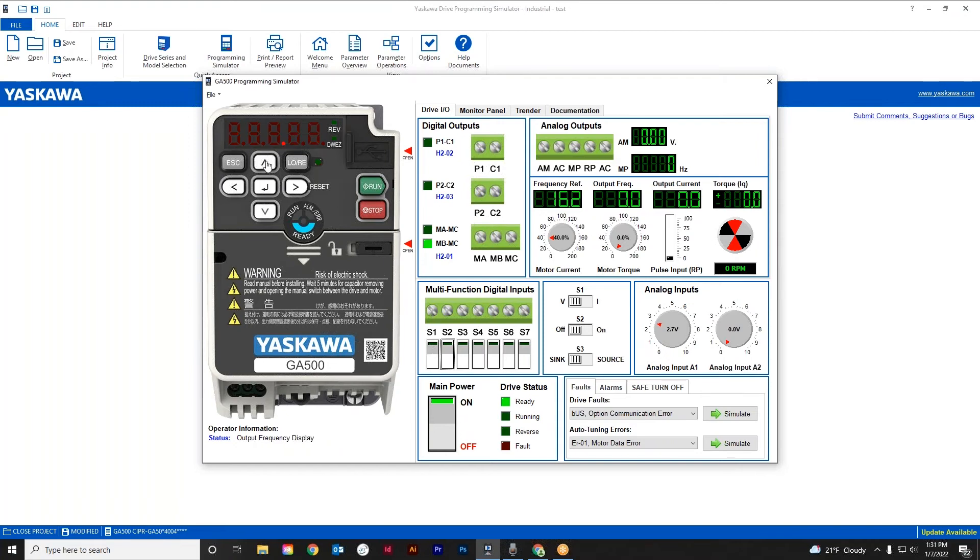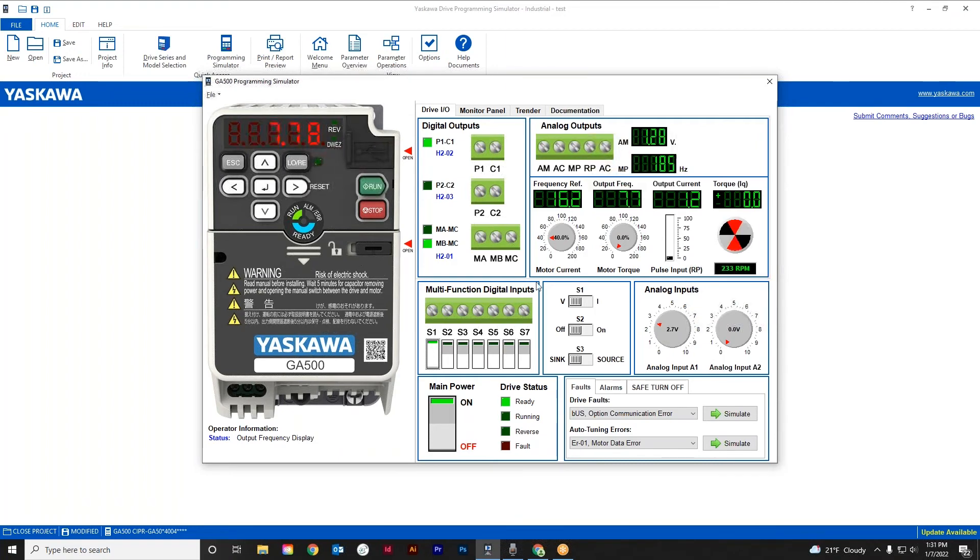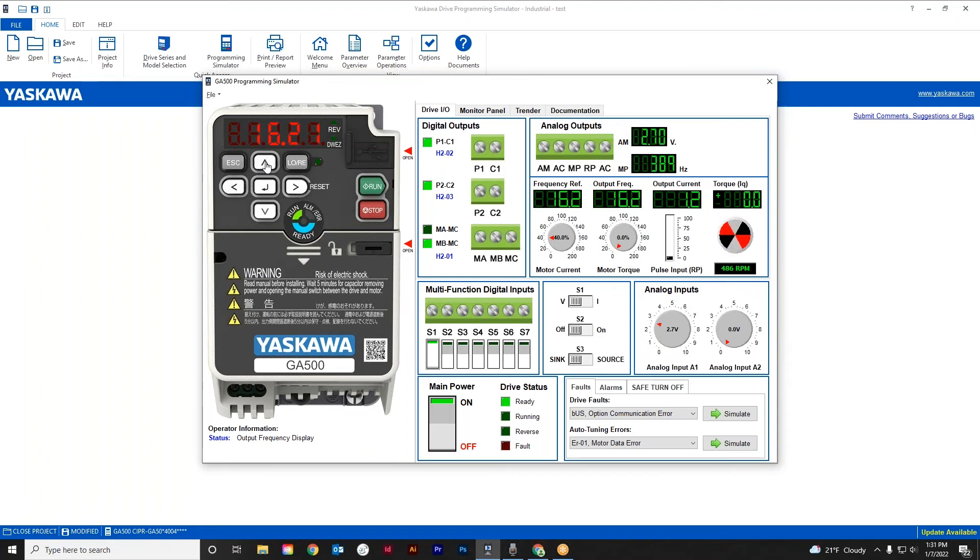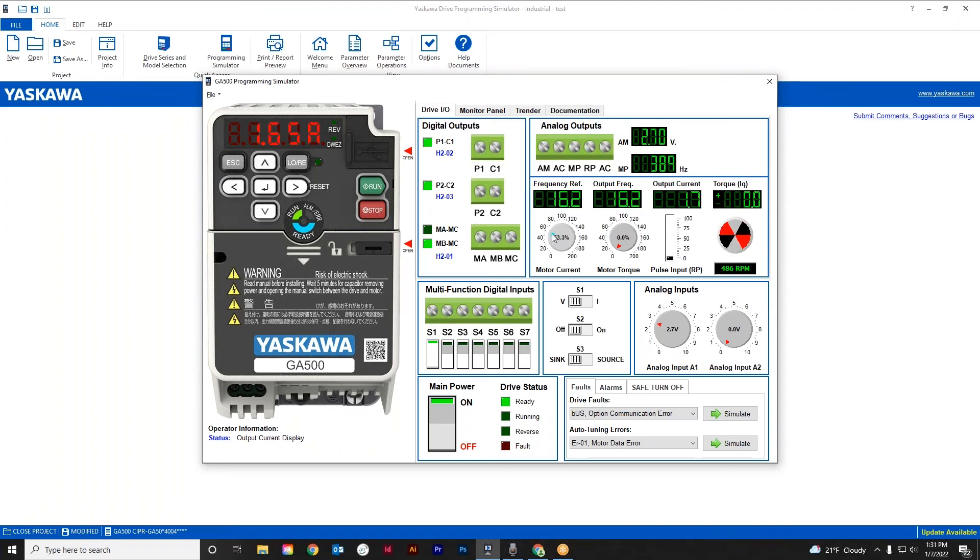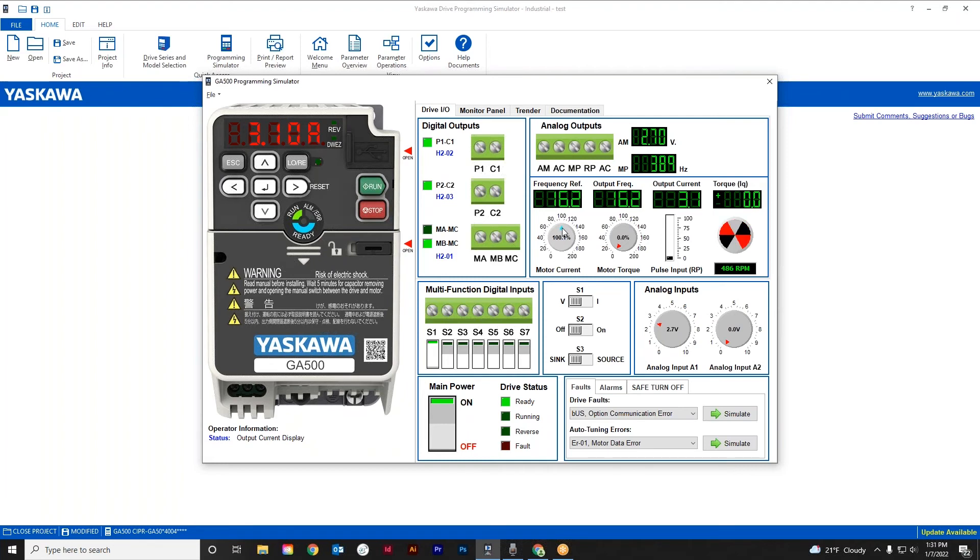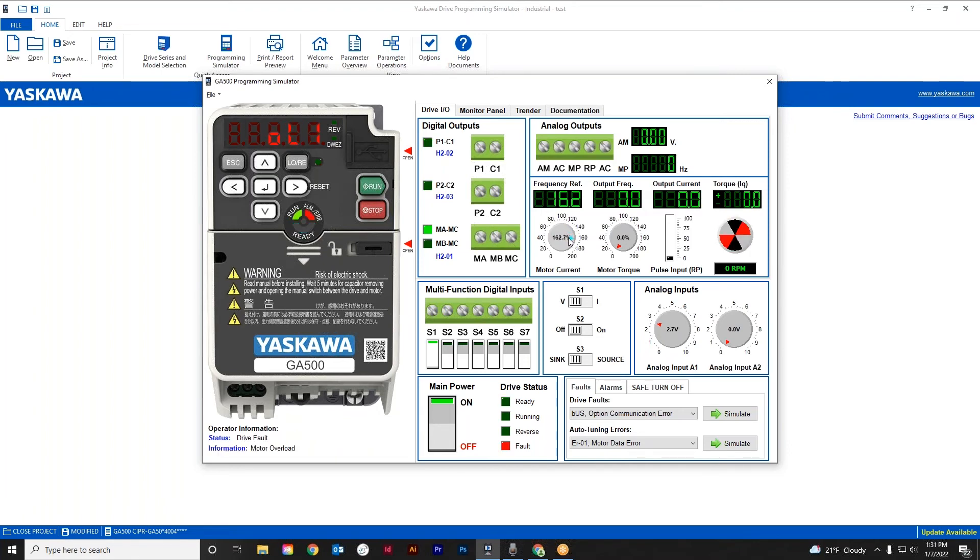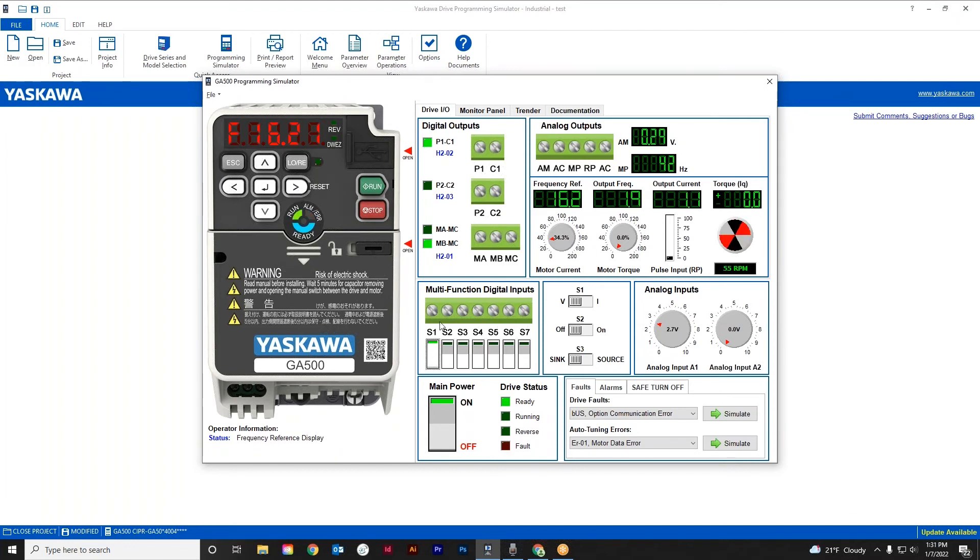What we'll do here is that we'll watch this ramp up at a slow rate at that 30 second rate that I programmed. Something to show you too is that here's some amps. This is a default setting. What's nice about this simulator is that you can actually play with the current. So if you have an issue and you want to see, okay, what's going on or what would happen if my drive were to draw excessive current, we can actually simulate excessive current too and see what the drive would trip on or how the drive would trip on the amps. So it's kind of nice. This one here, I'll crank it up and eventually we'll see an oL1 trip. Reset it and we're back in business again. So that's kind of nice. So you can simulate the output current fault as well.